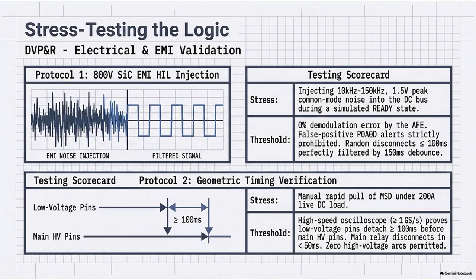Okay, that proves the wires work. Yeah, but what is the second end-of-line test? The second test is the physical validation of the hardware panic reflex we discussed earlier, the 50 millisecond hardware bypass. How do they test that? They hook the battery pack up to a massive testing rig and power the system up, simulating a fully ready state with lethal high voltage actively flowing through the closed contactors.